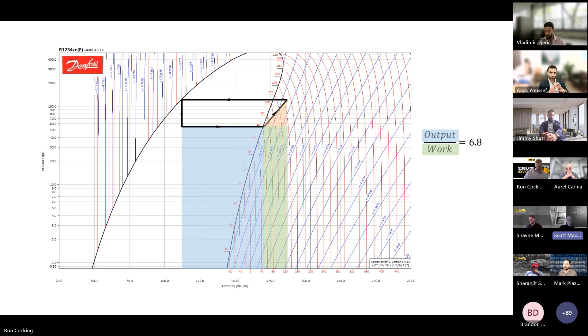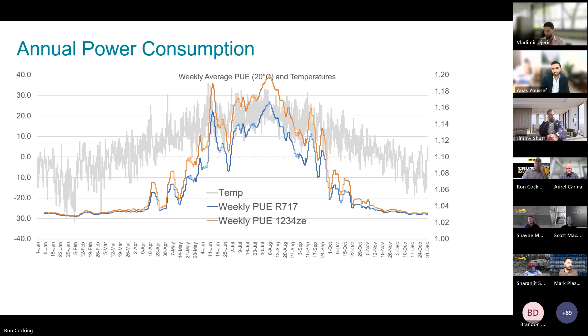So as it applies to PUE, power usage effectiveness, which we all talk about, what we've applied here is an R1234ZE chilled water system with free cooling, shown in red, and the same capacity system using R717 ammonia and free cooling in blue. It's overlaid on the annual ambient temperature fluctuations, and we're providing a weekly average PUE in a local Canadian municipality, delivering 20 degrees Celsius fluid out to the data center. And what we can see here is the PUE of the R1234ZE is always higher, worse than the R717 option. Next slide, please.